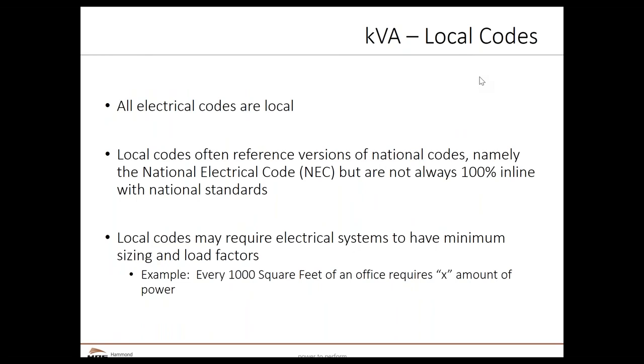Another big thing when sizing transformers is understanding that local codes can also dictate a minimum transformer size or minimum panel size. We often reference the National Electric Code, but local codes may also differ, and there are different versions of the NEC. Local codes may require electrical systems to have a minimal sizing or load factors — for example, in an office building, school, or hospital, for every so many square feet, a certain amount of power is required. You may calculate that you need 100, but the minimum sizing by code might be 125. Just something to keep in mind.